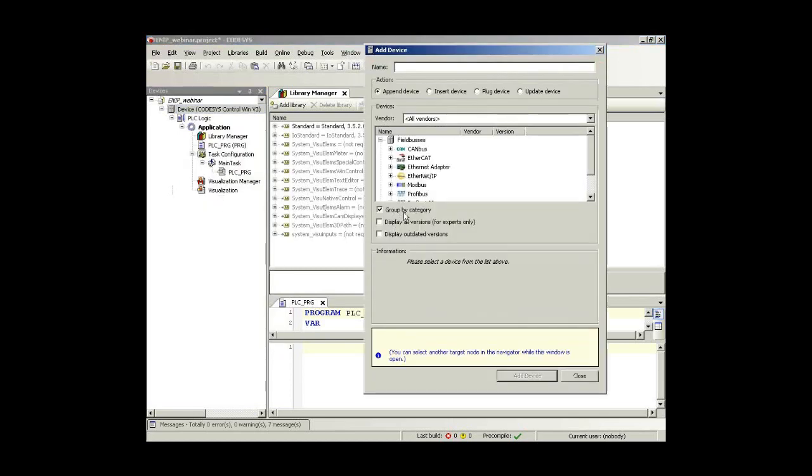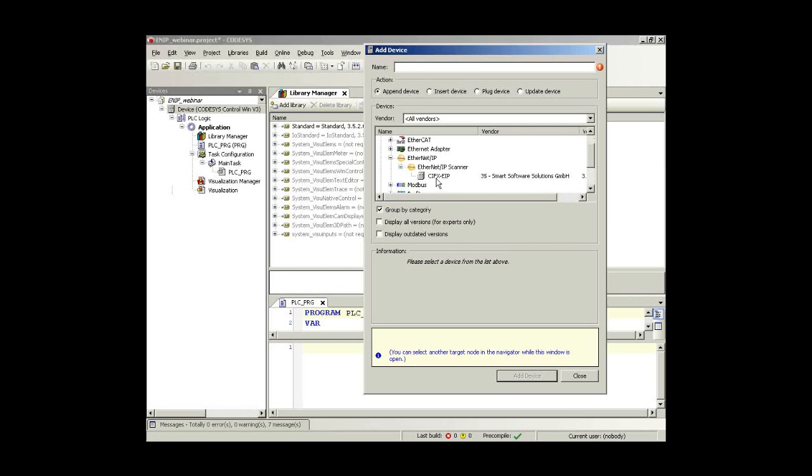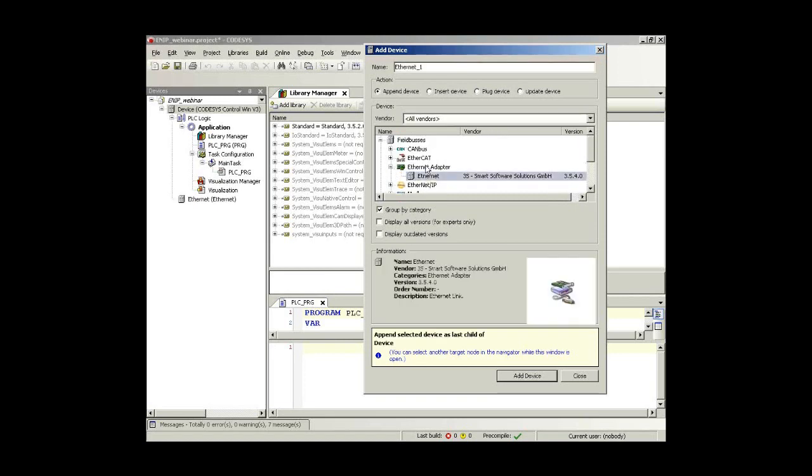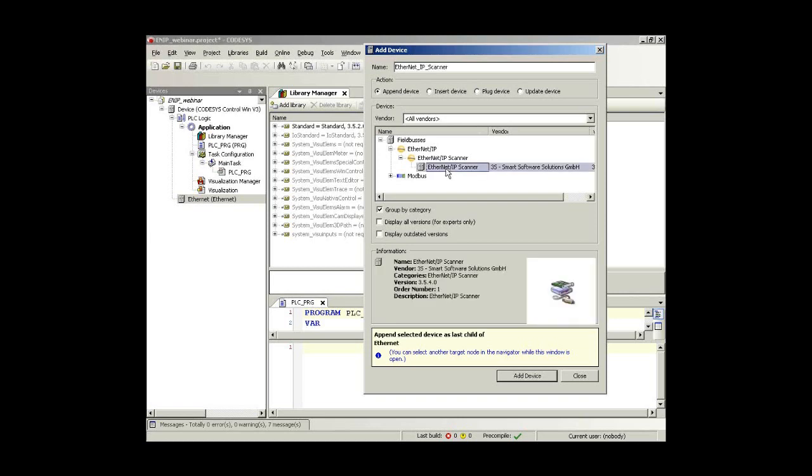Now you see that there is already an EtherNet/IP controller available. But if you click on that, we will see that this is the old solution using a special interface card, a Hilscher card with a CIF-X or a special NetX communication chip on board. This was the solution with a dedicated hardware. In this case, we do not want that, but we want to use a standard Ethernet port. So I go to the Ethernet adapter. I include that Ethernet adapter into my device tree.